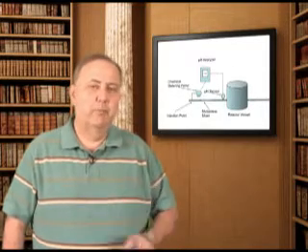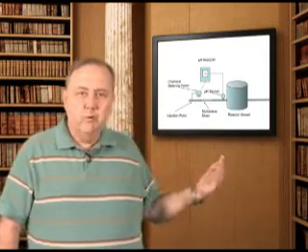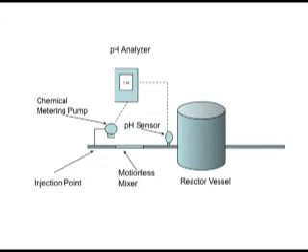What I advised the practitioner to do was to move the pH sample point to before the tank, and add an inline motionless mixer between the injection point and the sample point. This is a simple example of how important sample location and sample transport are.